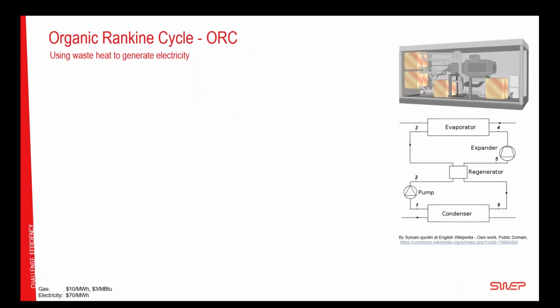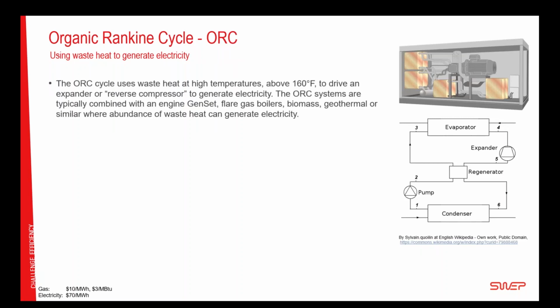Organic Rankine Cycle. There, I nailed it. ORC. The ORC system is very interesting. It's an old technology, but it's still hot. It uses high temperature waste heat, or high temperature heat, above 160 Fahrenheit, 90 Celsius or something, to drive an expander, or we can say a reverse compressor, to generate electricity. Since the ORC system requires so much energy, it's typically put together with an engine genset, as we discussed before, where you have flare gas that you cannot burn off, or you have to use it in some way, or you have biomass or geothermal, or any other situation where there is a large excess of heating energy.